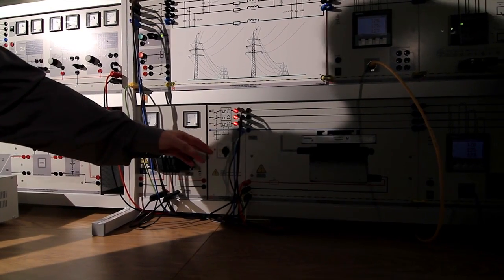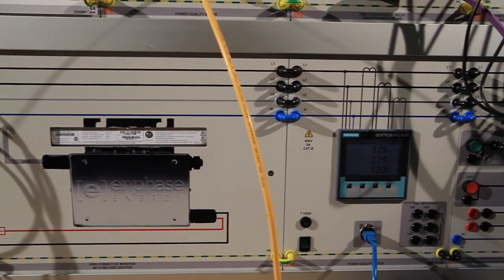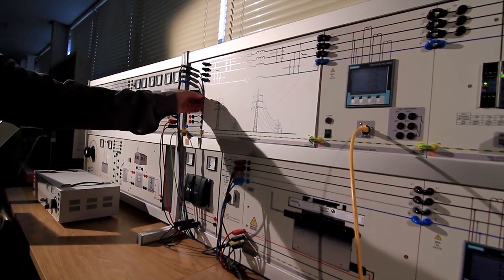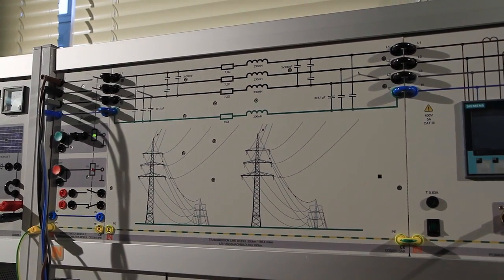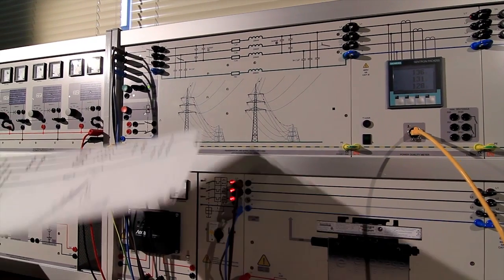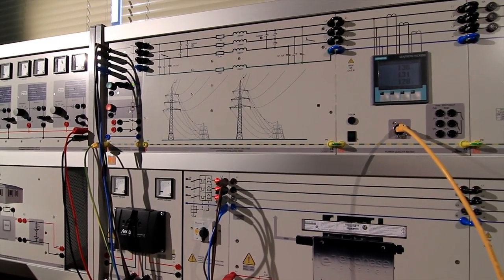This is the network inverter. The utility connection to the system is introduced through a switch. We have power from the utility that comes through the circuit breaker to the transmission line. The transmission line represents two possible models: medium length transmission line about 90 miles long, and if we remove the overlay mask, you can see the transmission line with a length of about 190 miles. The parameters of these two models actually change automatically and change the behavior of the system.